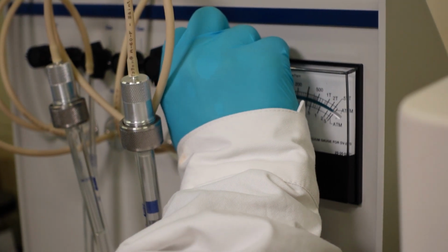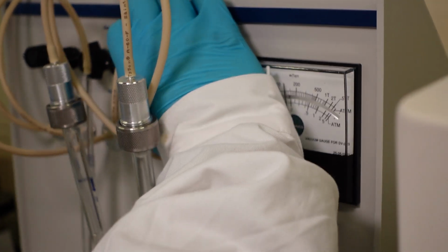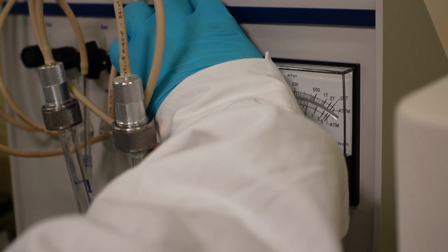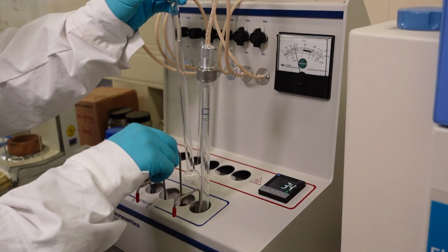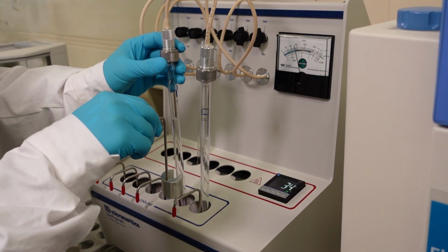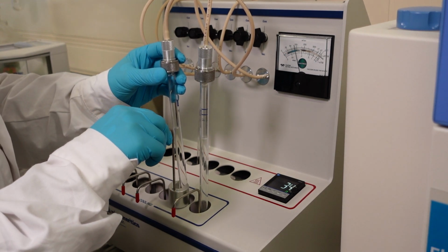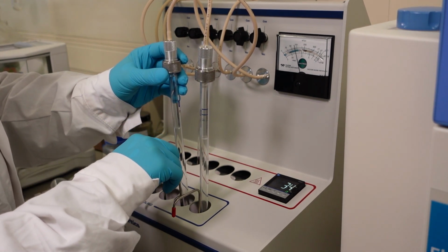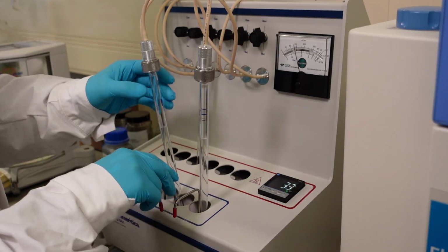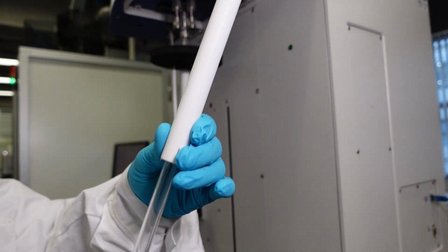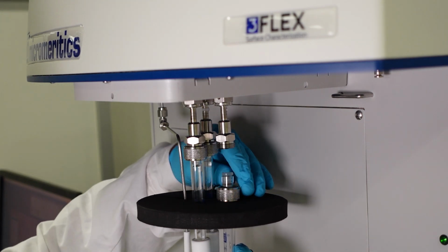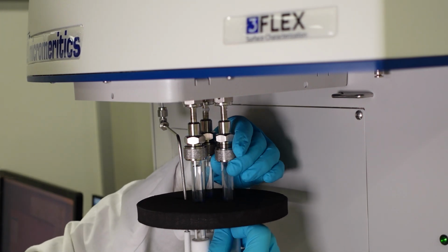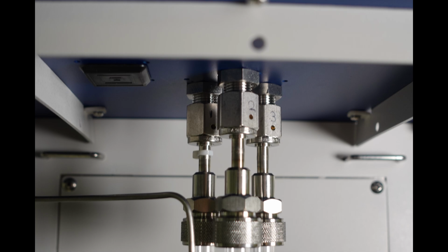After pretreatment is finished, transfer the tube to the cooling compartment. When the tube is cool enough, weigh the glassware containing the pretreated sample. This is done to ensure you have accurate data on the mass of the substance, which is an important parameter for the machine. The machine we will be using is the Micromeritics 3Flex. It can take 3 samples at once. It is important to know which sample corresponds to which one of the numbered ports.